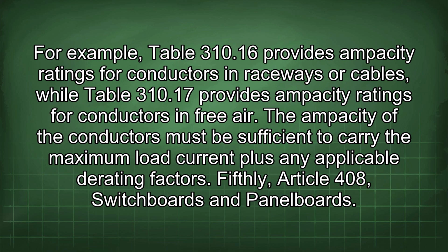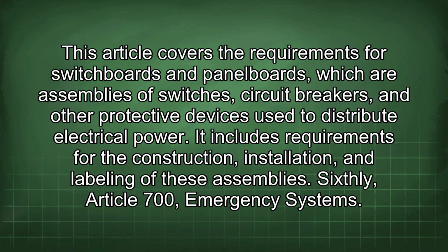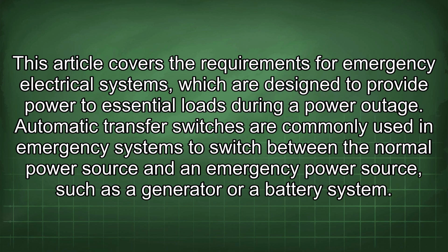Fifthly, Article 408, Switchboards and Panel Boards. This article covers the requirements for switchboards and panel boards, which are assemblies of switches, circuit breakers, and other protective devices used to distribute electrical power. It includes requirements for the construction, installation, and labeling of these assemblies. Sixthly, Article 700, Emergency Systems. This article covers the requirements for emergency electrical systems, which are designed to provide power to essential loads during a power outage. Automatic transfer switches are commonly used in emergency systems to switch between the normal power source and an emergency power source, such as a generator or a battery system.